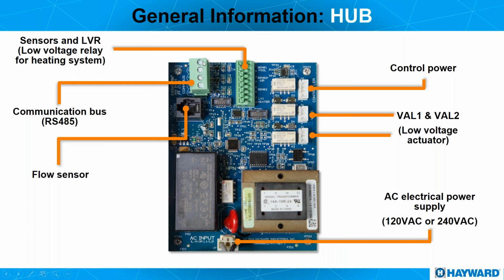And then on the left side, top left, we have a communication bus, RS485, where we're going to be connecting anything that communicates with the system through data. For example, variable speed pumps, our chlorinator, the sense and dispense system, which is the one for chemistry, pH and ORP, and also any other digital control that we add to the system.